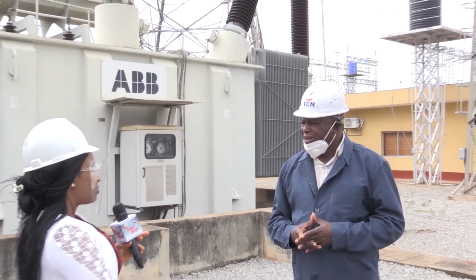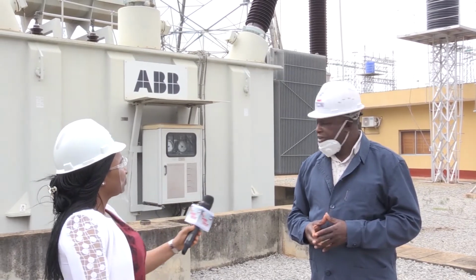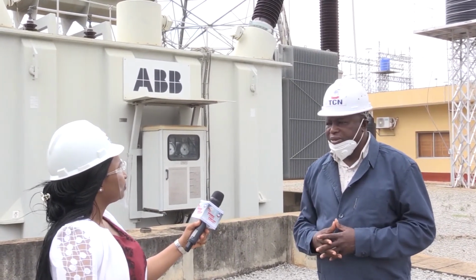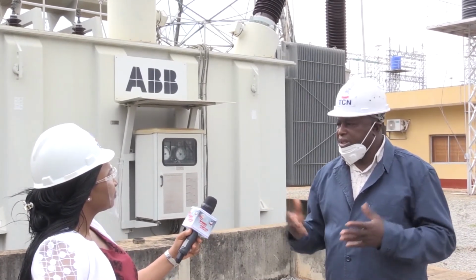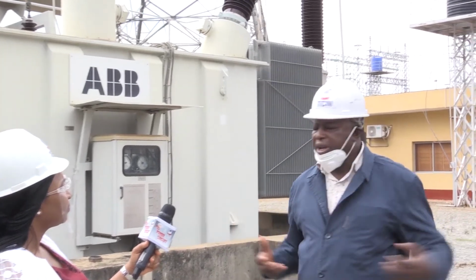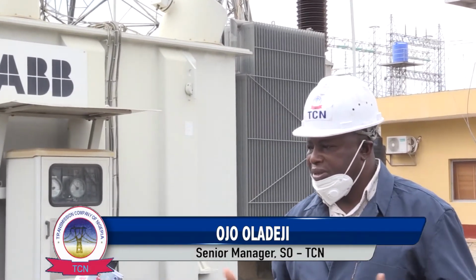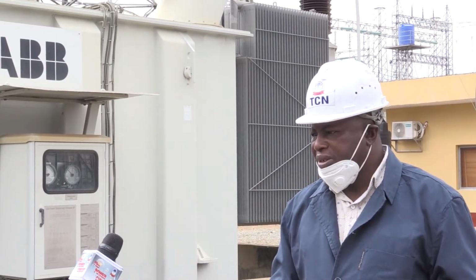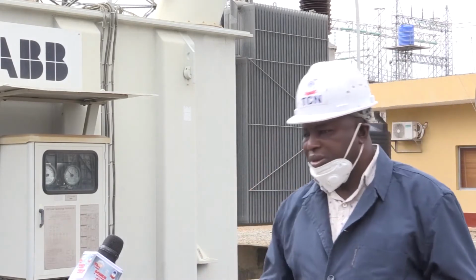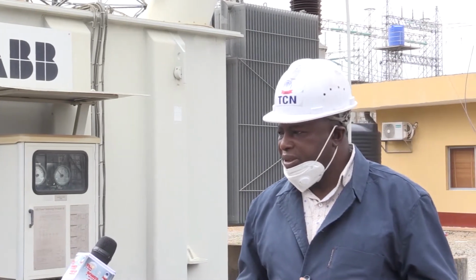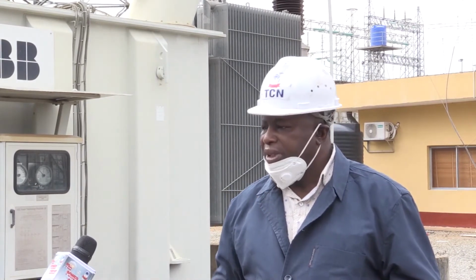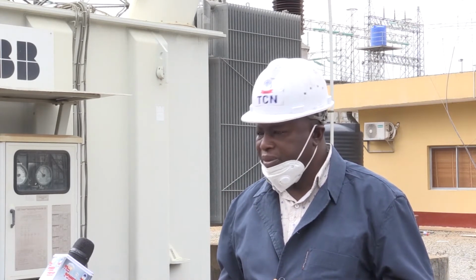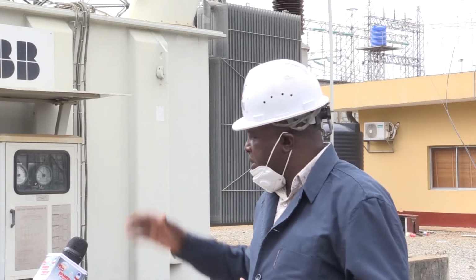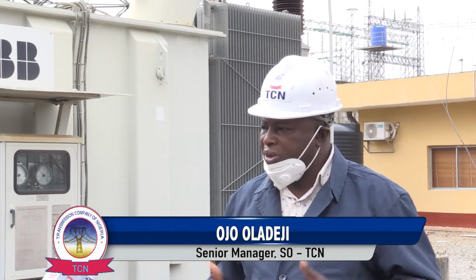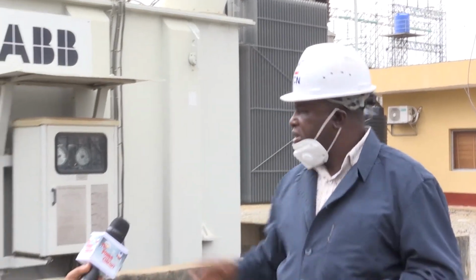Can we please know when this particular reactor was installed in this substation? Yeah, this reactor was installed about 2003. Everything was done when the station came up; all the equipment here was installed together with the reactor because it's very, very important. Just as you are asking me, one of the responsibilities of the reactor again is that when we have a system collapse and the system is coming back up, the initial voltage is always high, which is not normal. One of the instruments we use to lower the voltage before we pick up our loads, to bring the voltage to the desired value, is the reactor.